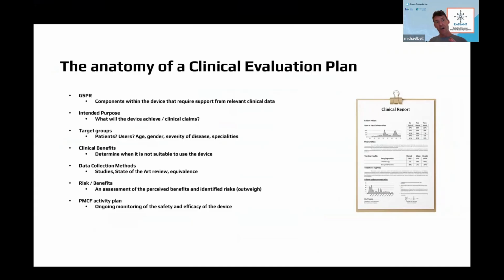And so the level of evidence you need to acquire, and the plan you need to set out, is going to be proportionate to that risk classification and other specific elements of your intended purpose statement. So certainly think about EU medical device regulations, in the UK, CE mark, and what's required with that. General Safety and Performance Requirements, or GSPR, is one of the key things. These are a list of safety and performance requirements where you're required to provide evidence to prove your device is safe to use. And there are many of them, okay?